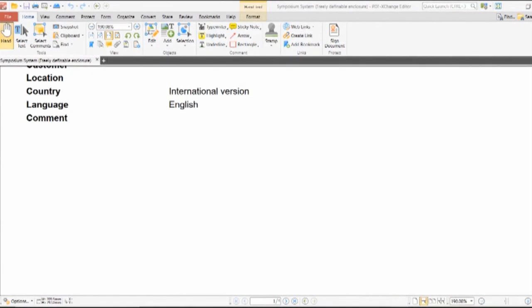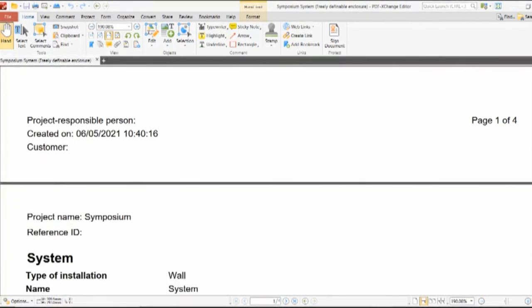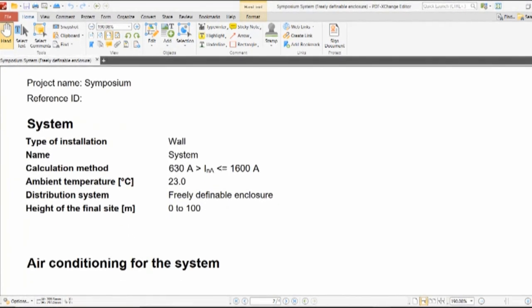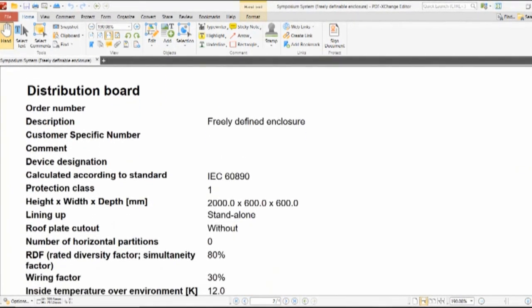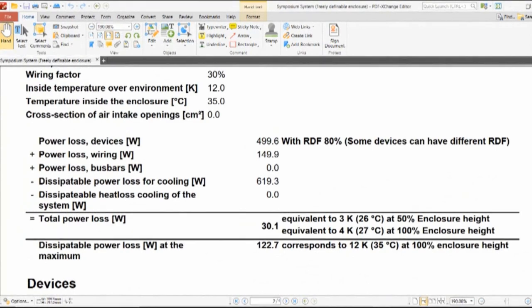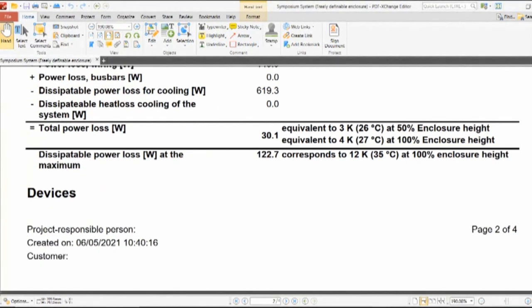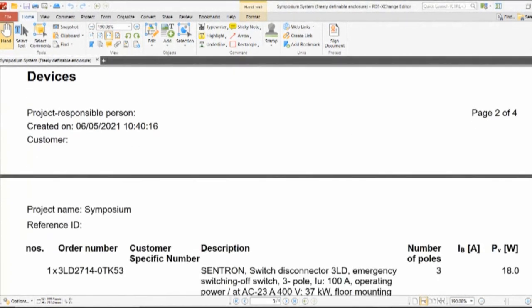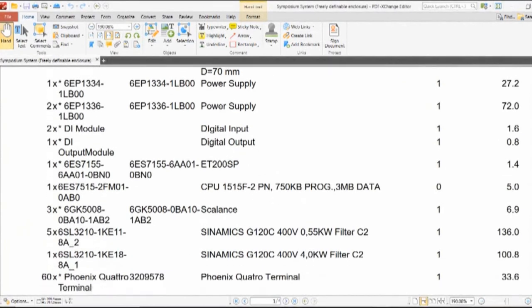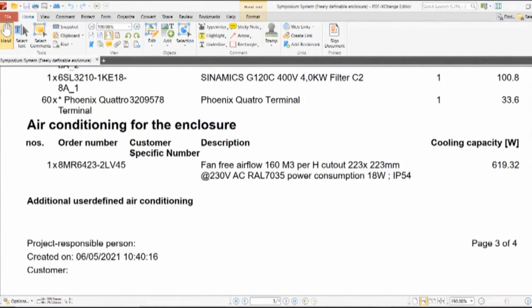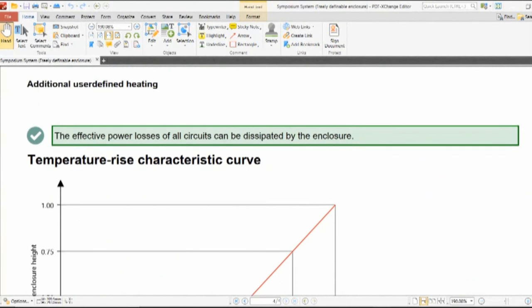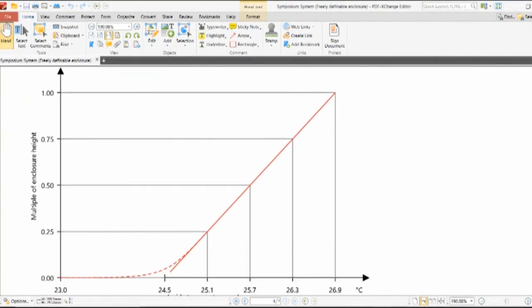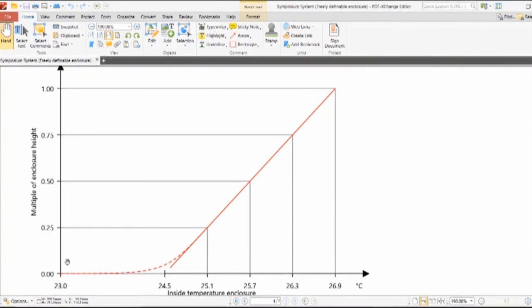So here's the technical file. This will tell us who did the calculation, when they did it. If we scroll down, the type of system. Up against a wall, for example. The size of our panel. The power loss data in terms of kelvins and watts. All of the products that are in there. The fan we're using, the cooling capacity of that fan. And last but not least, the temperature rise characteristic curve showing that our panel is within the temperature we want. And go ahead and add this now to your technical file.